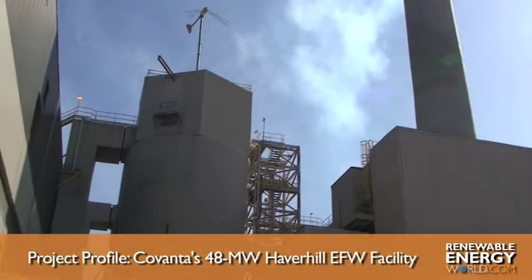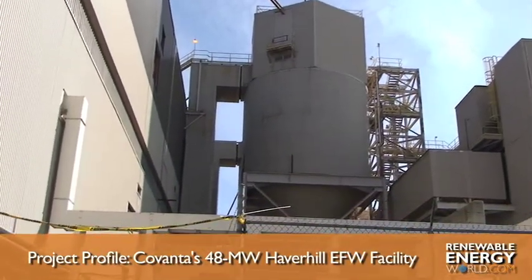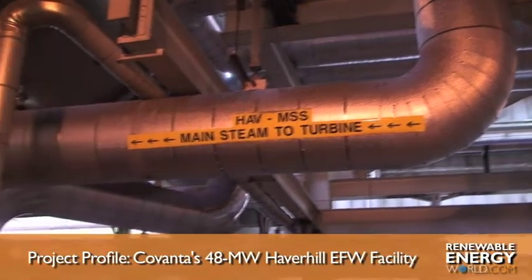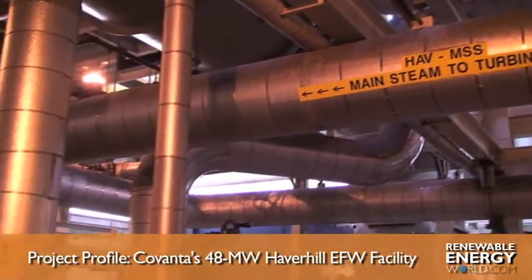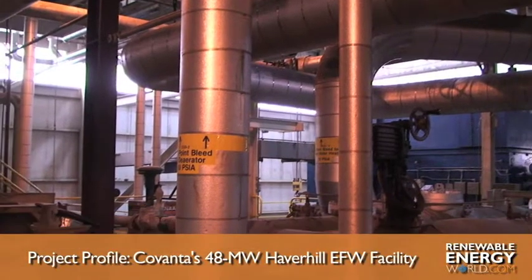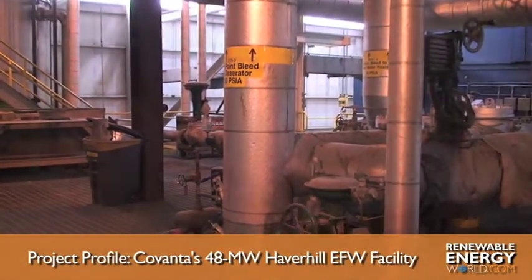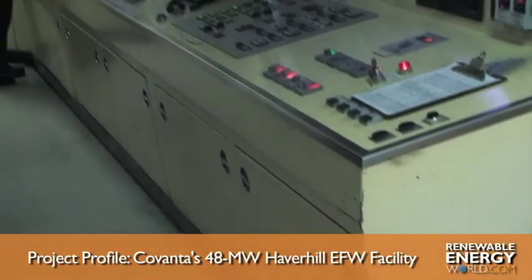The remaining gases produced by the boiler are cooled and travel through scrubbers and electrostatic precipitators, which remove more than 99% of particulates, including sulfur dioxide and hydrogen chloride. Ash produced in the combustion system process is wetted and transported to a lined landfill to prevent it from reaching the water supply.